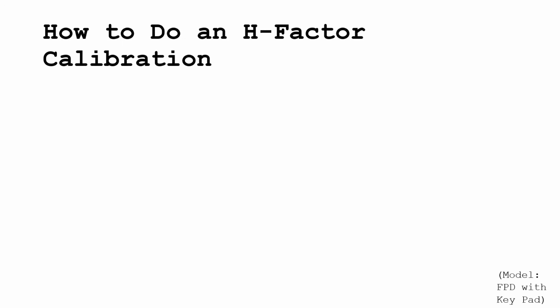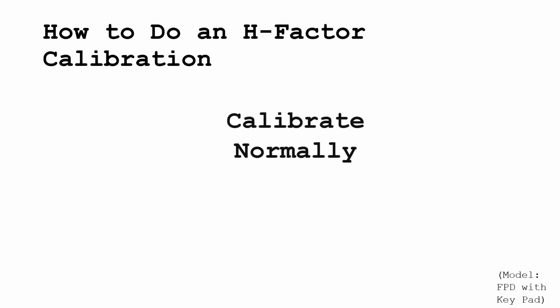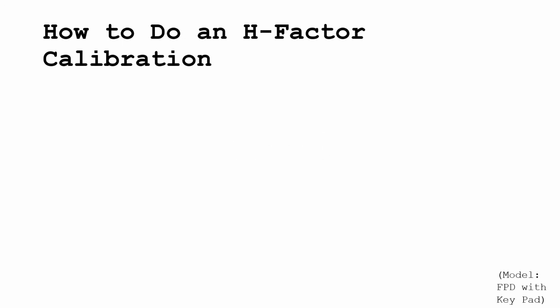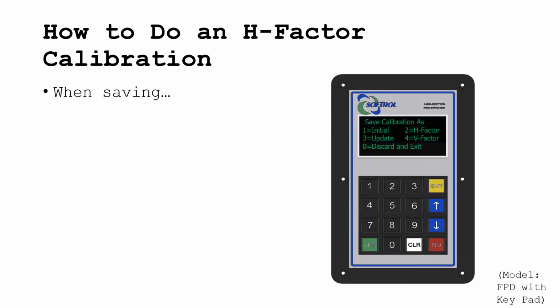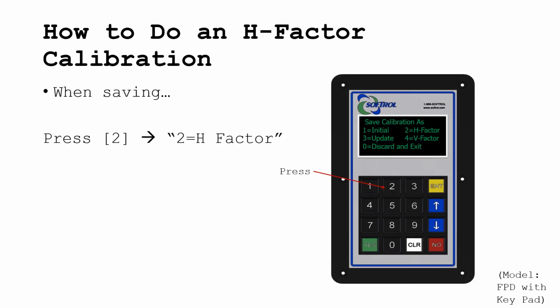To do an H-factor calibration, you calibrate as you normally would, but when you are saving the calibration, you press the 2 key to store the calibration as an H-factor calibration. This is very important or else the calibration will change and be overwritten.